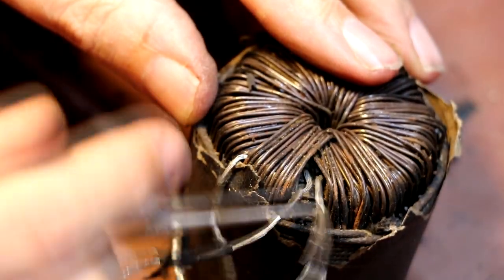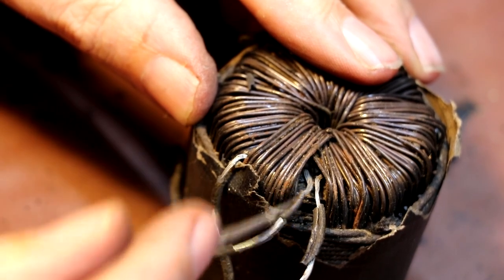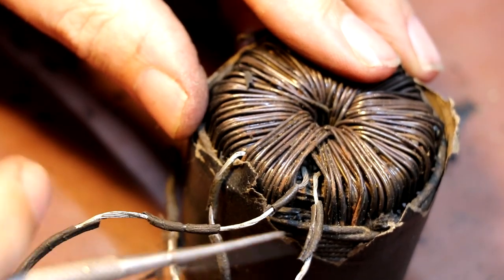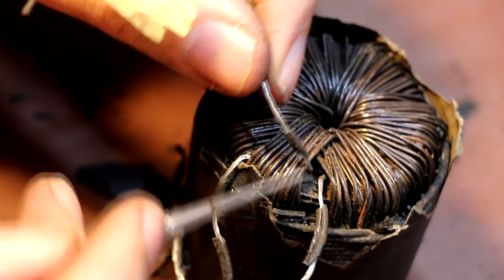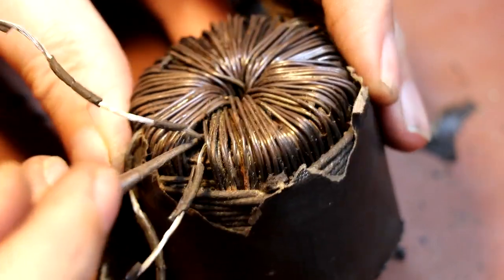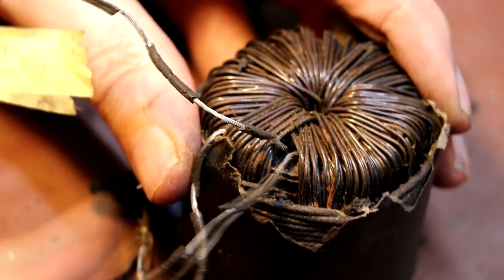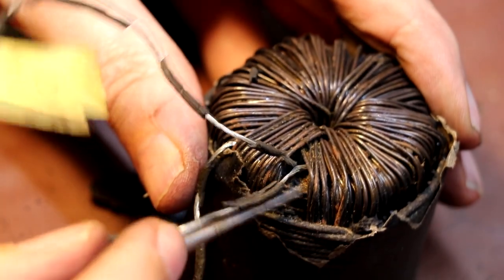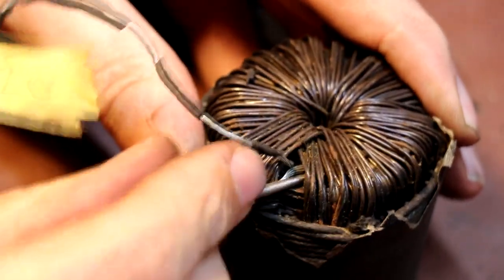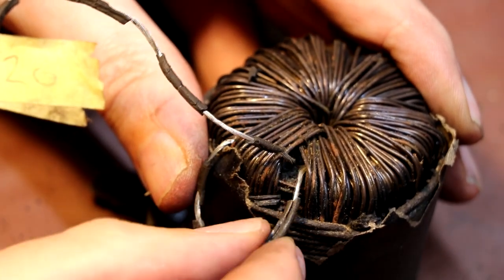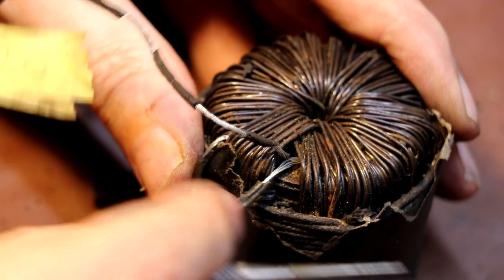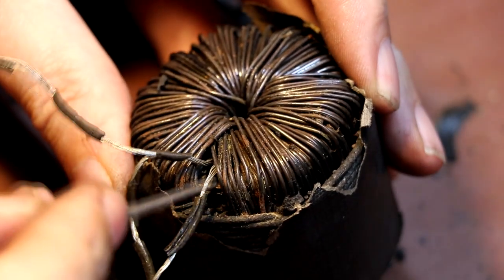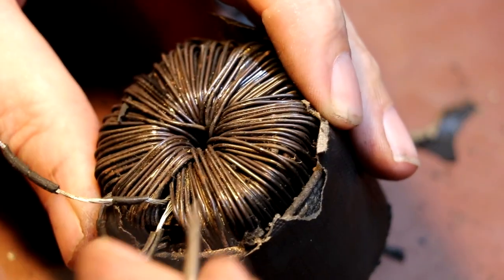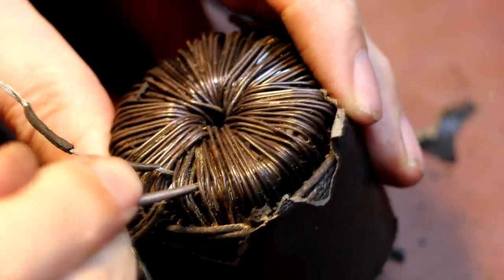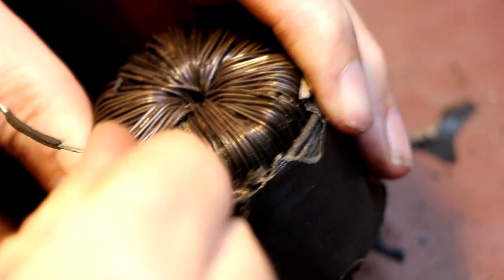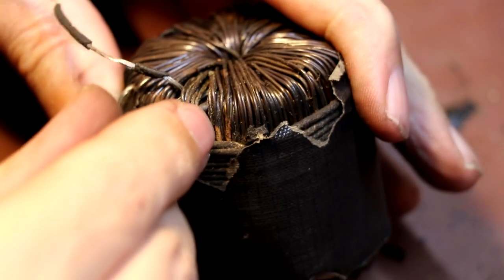Actually, all the insulation has completely come off these wires, and I just don't see any way that we'll be able to insulate them. Now, certainly I think I might have been able to get at this winding here and maybe put some insulation as it enters the bobbin. But this other wire next to it does run under this steel material for quite some way, and it runs under it without any insulation. All the insulation has gone away, and you'd have to take the steel windings off to actually expose the part of the transformer to get at. I'll tell you what, I'll keep prizing away. Maybe we'll be able to see it.